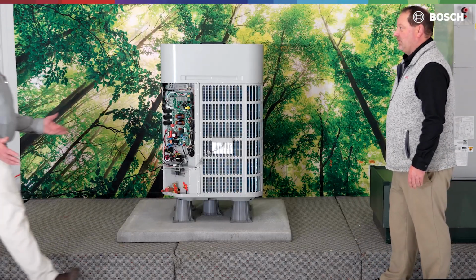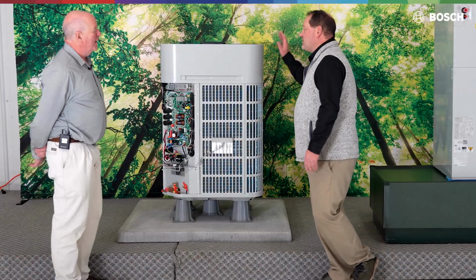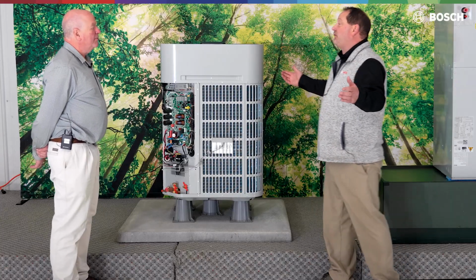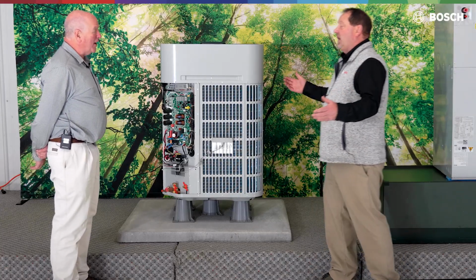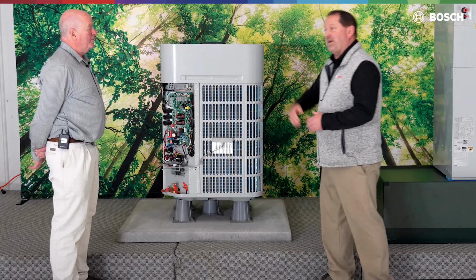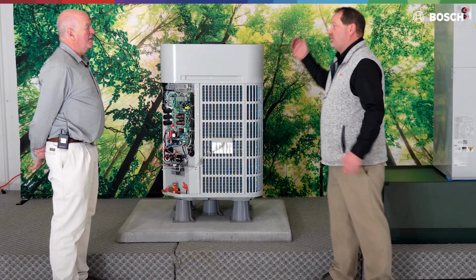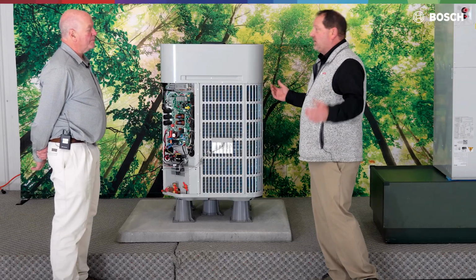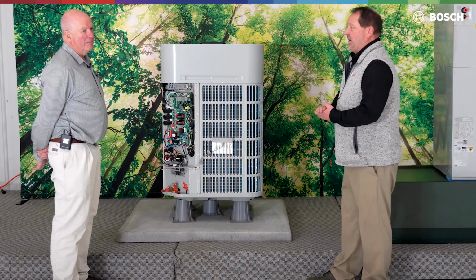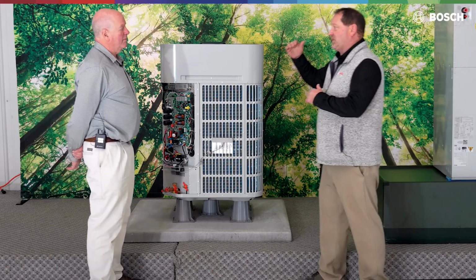How much can we physically go? With this particular product, we've got as much as 150 feet of line set to work with. 150 feet? 150 feet. And of that, we've got 50 feet vertical to work with. So depending on my horizontal length, that may affect my vertical length. If I have a long horizontal run, my 50 feet is going to have to come down.